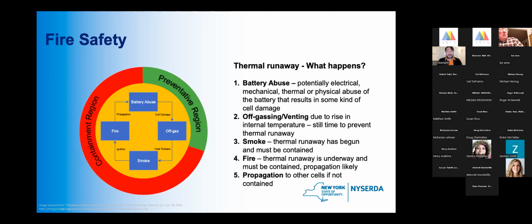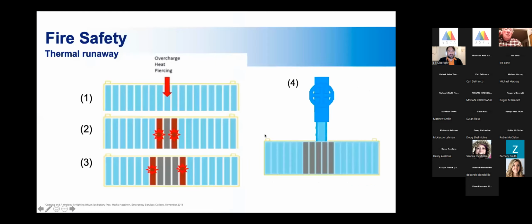Typically, the way battery cells enter thermal runaway is through some form of abuse. You will not see thermal runaway in the normal charging and discharging of batteries. Then we'll see some off-gassing, probably some smoke, though not always. Fire will then come next, and then we have the concern about the fire propagating to other cells. Again, really looking at containment once we've entered thermal runaway, but there are things we can do to prevent it.